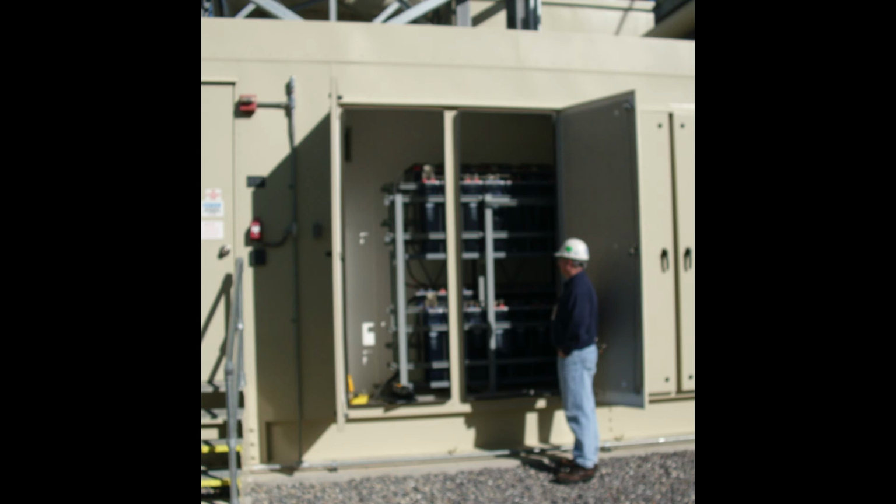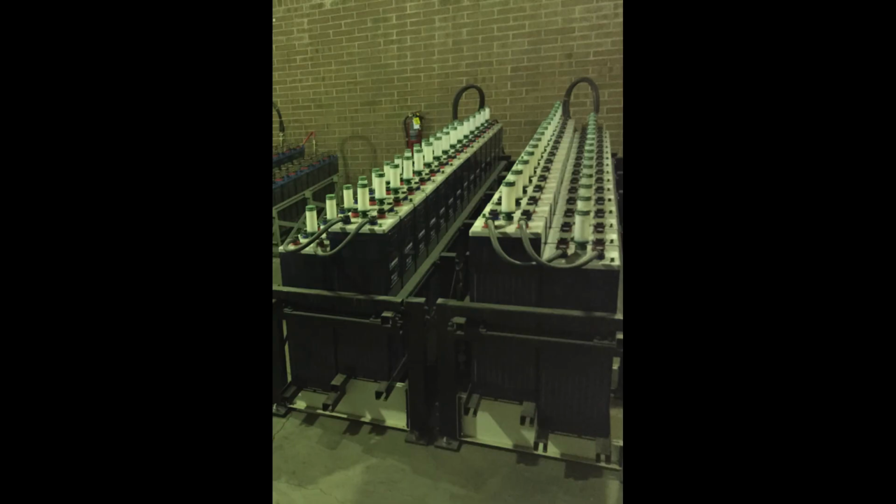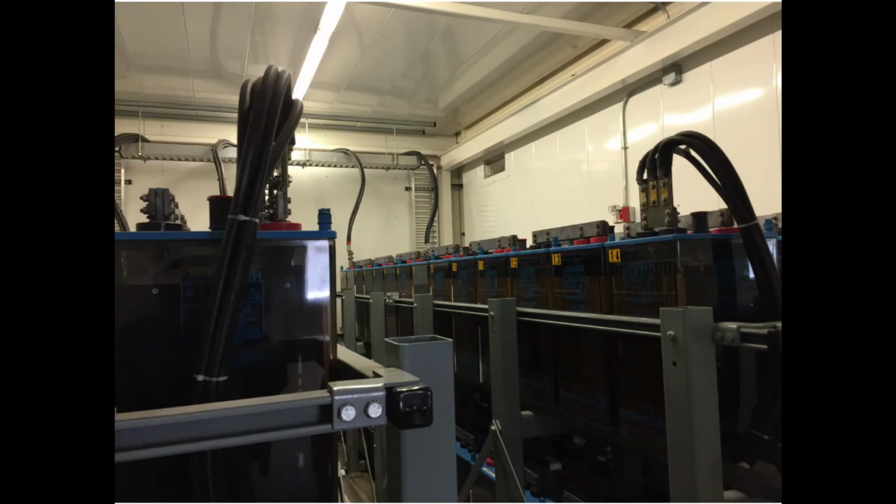If you cannot locate the path to ground on the cell while it is in the tray, the next step will have to be that the battery is removed from service, so that you can pull the cell out from the tray in order to inspect the cell in more detail. Sometimes there will be a leak develop on the side of the cell where the cover and the jar are sealed together, but you just can't see that with the cell in the tray. To look at this area, the cell must be pulled partway out of the tray, which means to do this, the battery needs to be removed from service.